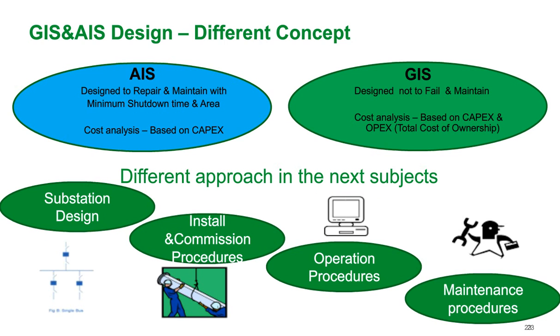Air-insulated switchgear is designed to maintain and repair and minimize shutdown time in that area. The main deciding factor for air-insulated switchgear, in the cost analysis at least, is CapEx. If you're not looking at operating expenditures, then CapEx is going to be the deciding factor for air-insulated gear. On GIS, it's designed not to fail and not to maintain. So your cost analysis becomes twofold, where you base it off of CapEx, how big your e-house or your building has to be and how expensive your switchgear is, and also analyzing the operating expenditure, so how you can reduce the cost of having to maintain switchgear, and over time looking at the probability of faults. If you can reduce the probability of faults, you can drastically save on possible future downtime as well.